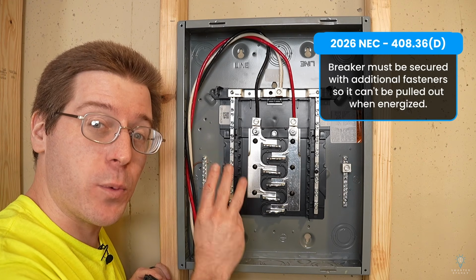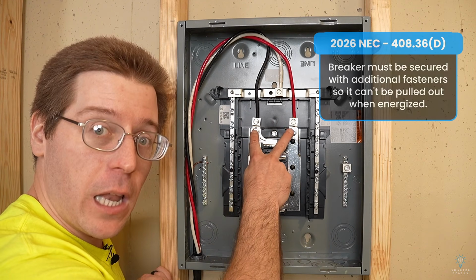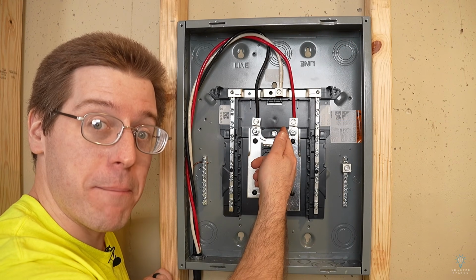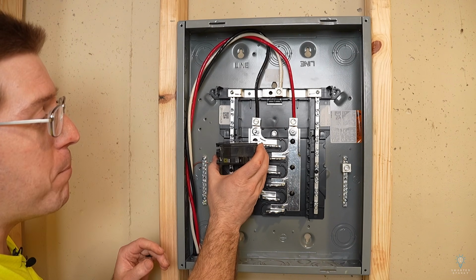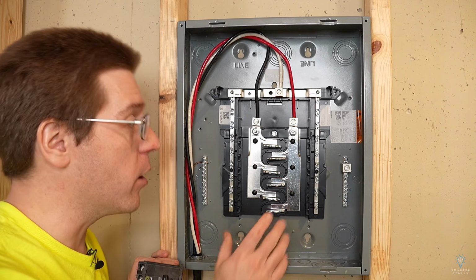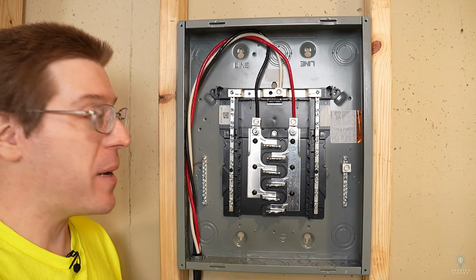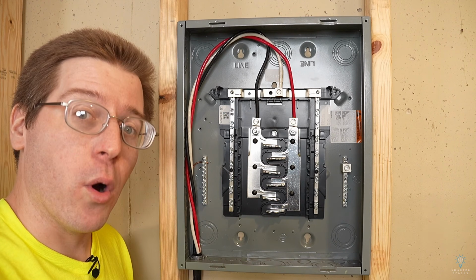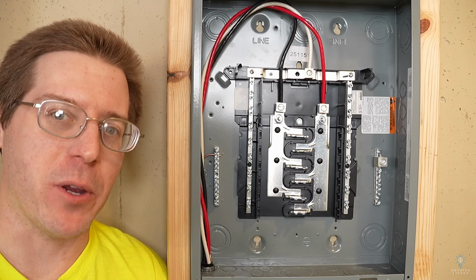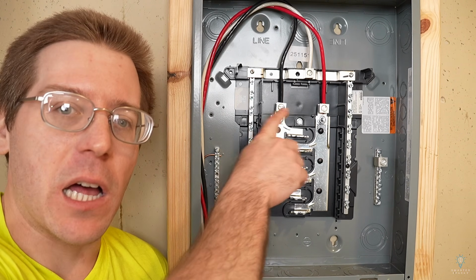So there's actually 3 ways we can feed a sub panel. Main lug, you could pass through a main circuit breaker, or you could backfeed a branch circuit breaker to energize those bus bars. Typically, main lug is going to be the cheaper overall solution. One more boring topic we need to talk about real quick is lug capacity.